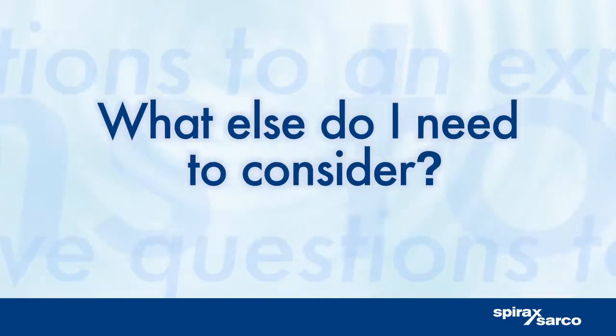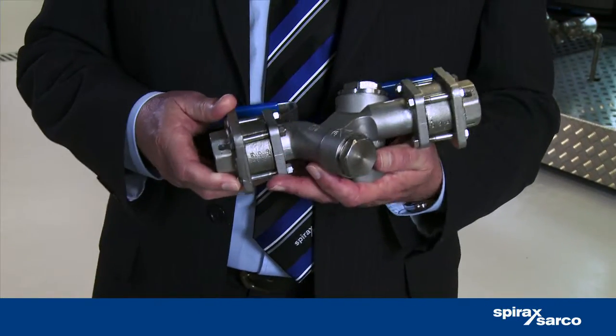What else do I need to consider? It may seem obvious, but steam traps do need to be fitted correctly. Incredibly, some of our survey engineers find steam traps fitted upside down. There are other installation rules, like ensuring that the steam trap is fitted below the condensate outlet. It's also a good idea to fit traps using a trapping station like this STS 17 to simplify maintenance. Finally, a regular steam trap survey is a really good idea.